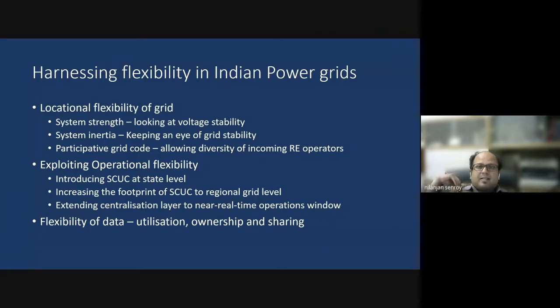However, at this stage, it is not very wise to rely on grid forming converters, as minimum available fault current levels should be satisfactory even without their contributions. Then finally, the system strength, if it is low at some point, must be enhanced by stabilizing the voltage using FACTS devices and by reducing the grid's internal impedance. So this can be achieved by modifying the dispatch so that a minimum number of synchronous generators in that neighborhood should always remain online. We can also convert retiring thermal generators into synchronous condensers. And of course, if you're looking at islanded grids, then grid forming converters can be a very key source of strength in those islanded grids.